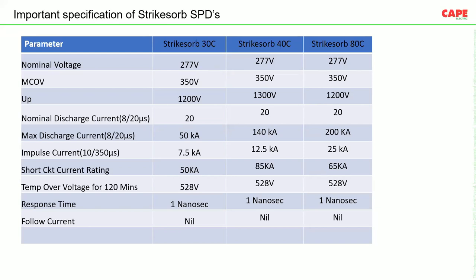When I'm telling you these values, 50, 140 and 200 kiloamperes, this is per pole rating. This is not the total rating of four poles. This is per pole rating. Impulse current rating is 7.5 kiloampere for Strikesorb 30, 12.5 kiloampere for Strikesorb 40, and 25 kiloamperes for Strikesorb 80. Now again, we have tested Strikesorb 80 with higher rating also.